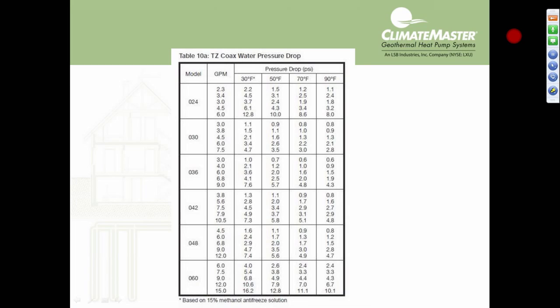Brian DeJong asks, do you feel that marginal loops will be more severely impacted with a variable speed pump unit? It's a good question. That'd be a case-by-case scenario. I would think it's not going to be any more impacted than with single-speed pumping. You're still going to have to pay attention to what kind of flow rate is going to be necessary through that particular loop. You may want to adjust your delta T lower based on what that loop configuration is. So it's a tough question to directly answer because it's a case-by-case scenario, and I would highly recommend that you run through our design tools, being our GeoDesigner. You can run backwards through the GeoDesigner tool in a retrofit application, and our pressure drop software has our new units in there so that you can verify where your Reynolds number is as far as turbulent flow. So again, good question. If you're running into a problem like that you don't feel real comfortable with, please reach out to your distributor or to our folks here at Climate Master.